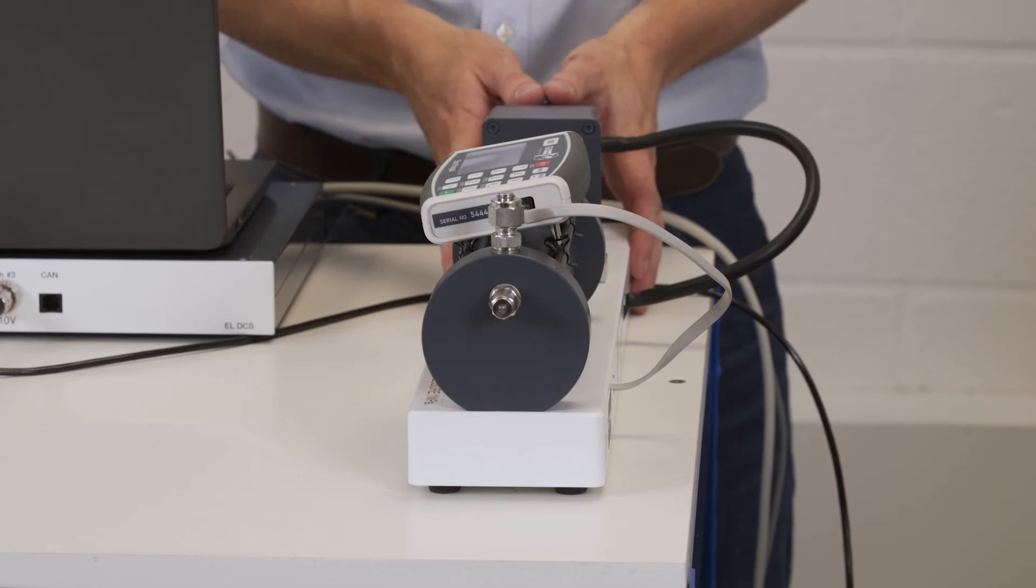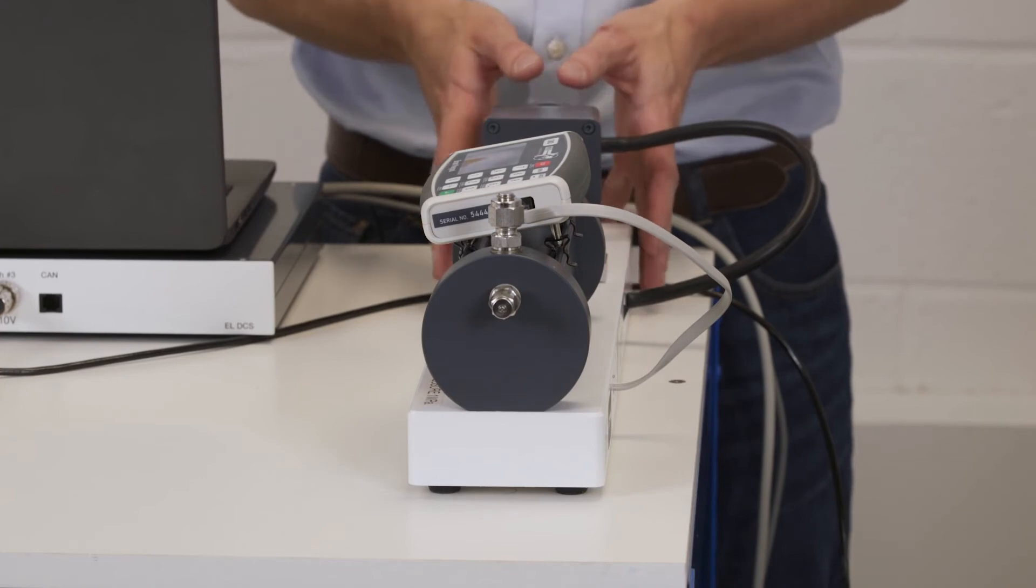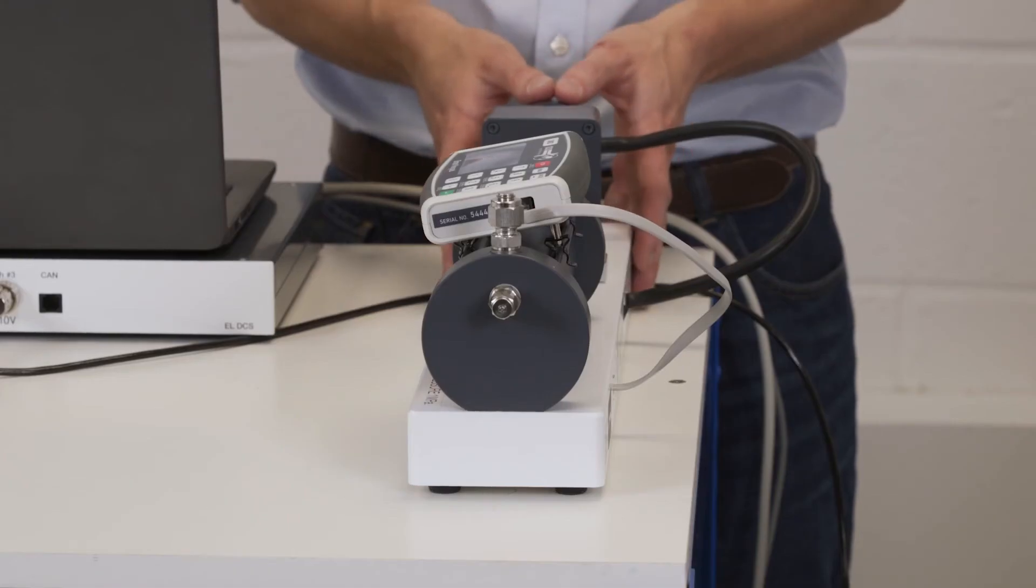The pressure controller is used for our back pressure connection, allowing us to generate pore pressure. This is our enterprise pressure controller ranging up to 1MPa. Other options are available such as our standard version 2 controller which will go up to 4MPa and our advanced pressure controllers which go up to 4MPa as well.